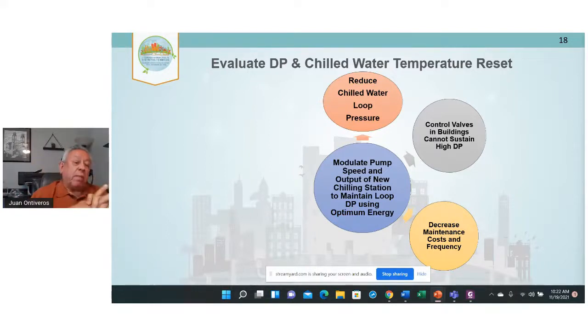The other thing is that by modulating flow, the speed of the chillers and the pumps, you improve your maintenance costs by adjusting how often you do maintenance. Because by not running them at full load all the time, they're running cooler, and so they're going to last longer. That's another advantage. By doing this you also improve your plant performance and reduce your pumping costs.